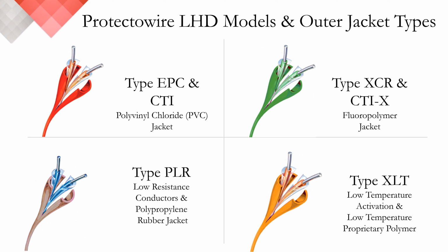heavy industrial applications. Type PLR is specific to our low resistance detector and is a polypropylene rubber-based jacket. It's UV stabilized, so it too is suitable for outdoor applications and also resists many of the same chemicals, oils as the XCR jacket and provides excellent flexibility in low temperatures. And finally, Type XLT is our most recent development and stands for extreme low temperature. This is our lowest rated jacket, which is rated to minus 60 degrees Fahrenheit, and is available only with our 135 degree detector. Offered both in PHSC and CTI series, this particular product was developed specifically for the industrial freezer market.